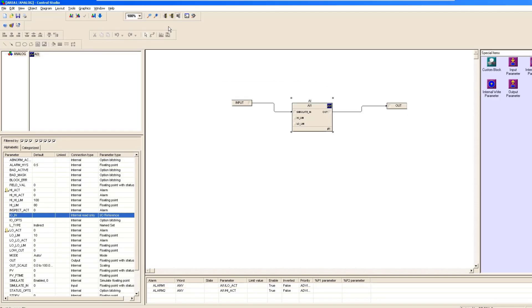You can select the type of alarm — whether it's Critical, Warning, or just a Log — and you can set the priority based on the critical nature of that alarm. In this session you learned how to get your analog signal and how to process it in the logical side of DCS. There is another side which is the graphical part, where you get that analog signal and display it on DCS screens. If you're interested, write a comment and hit the Like button, and I'll make a tutorial on how to link the process parameter from field instrumentation to the graphical part. That's all for today — take care and Allah Hafiz.